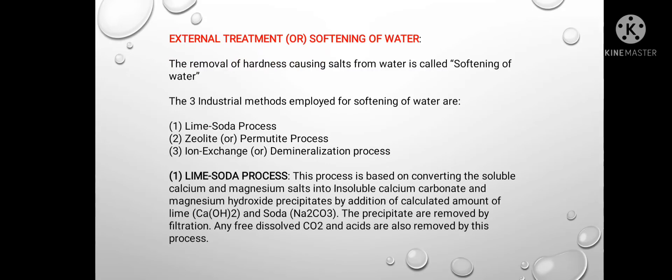Now we will see external treatment, also known as softening of water. The removal of hardness-causing salts from water is called softening of water. The three main industrial methods employed for softening of water are: lime soda process, zeolite or permutit process, and ion exchange or demineralization process. First, lime soda process — this process is based on converting soluble calcium and magnesium salts into insoluble calcium carbonate and magnesium hydroxide precipitate by addition of calculated amounts of lime and soda. The precipitates are removed by filtration. Any free dissolved CO₂ and acids are also removed.